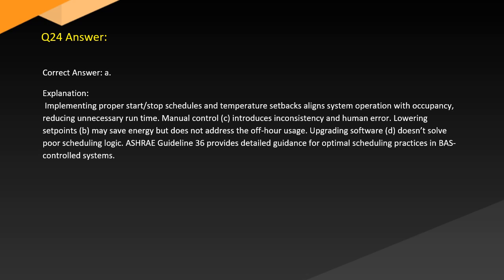Answer. Correct answer: A. Explanation: Implementing proper start-stop schedules and temperature setbacks aligns system operation with occupancy, reducing unnecessary runtime. Manual control, C, introduces inconsistency and human error. Lowering setpoints, B, may save energy but does not address the off-hour usage. Upgrading software, D, doesn't solve poor scheduling logic. ASHRAE Guideline 36 provides detailed guidance for optimal scheduling practices in BAS-controlled systems.